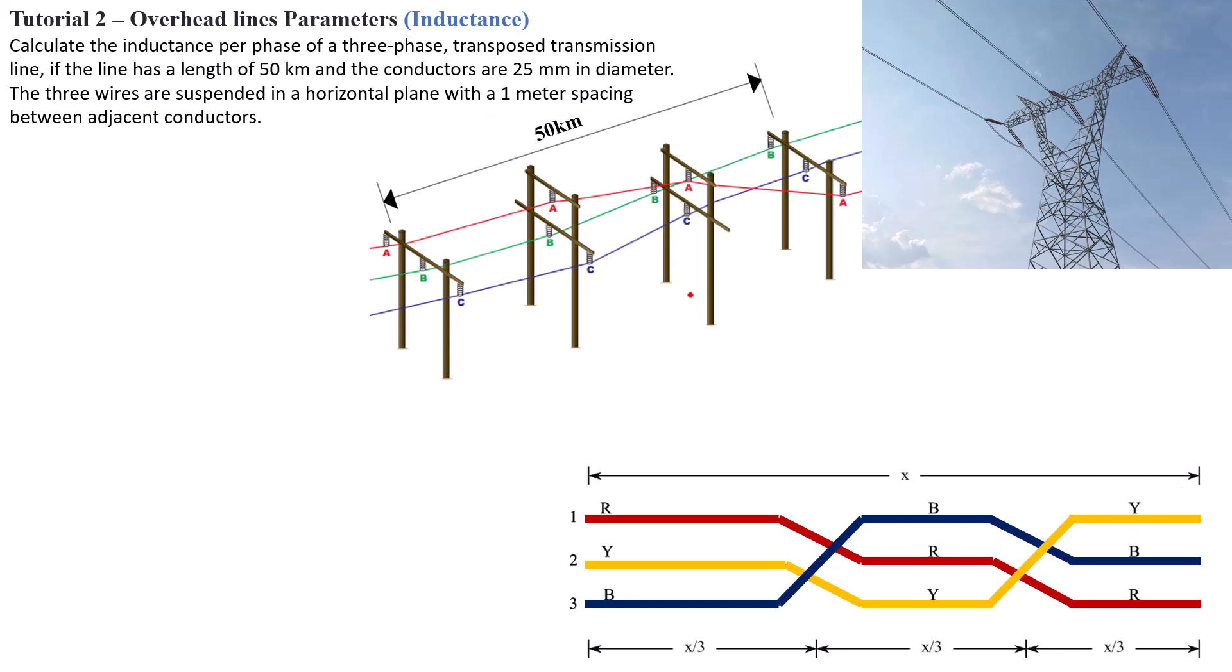Now just as we solve the resistance of the line by calculating the resistance per kilometer, the inductance is also calculated per kilometer given with a general formula: L equals 0.05 plus 0.2 times ln, the natural logarithm of dE divided by R. So the answer will be in millihenry per kilometer.